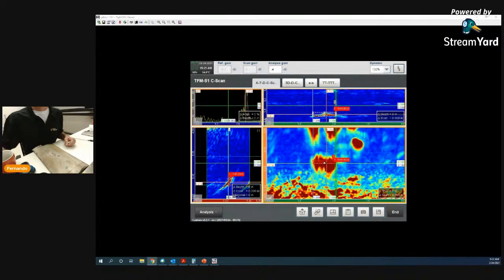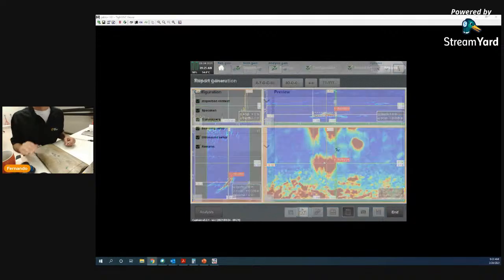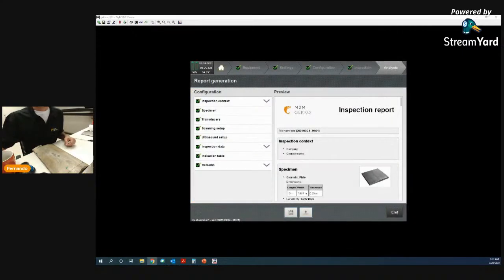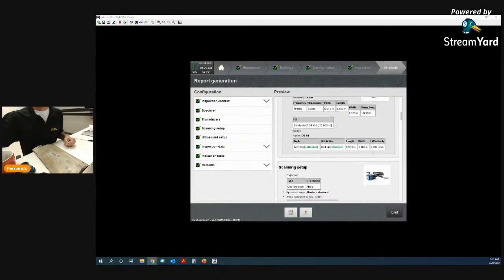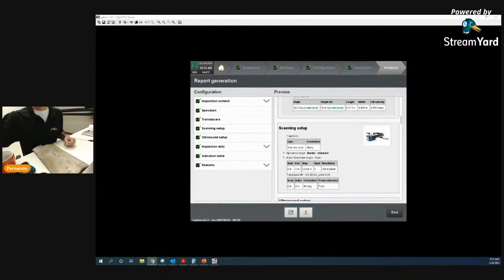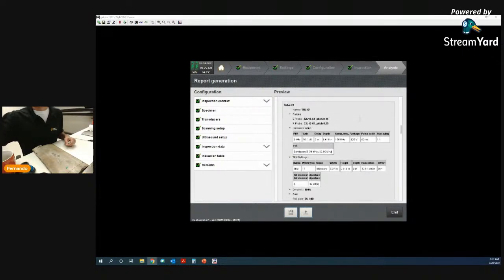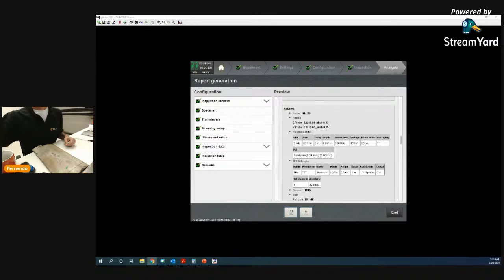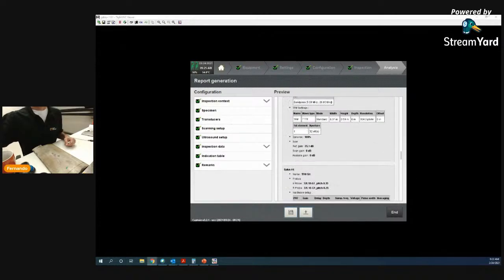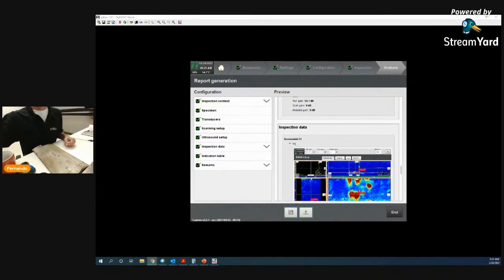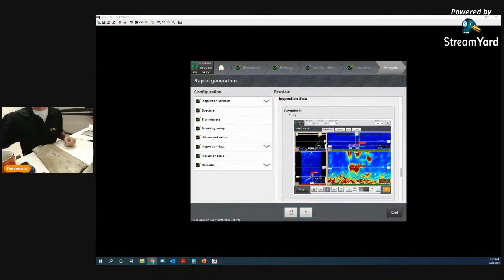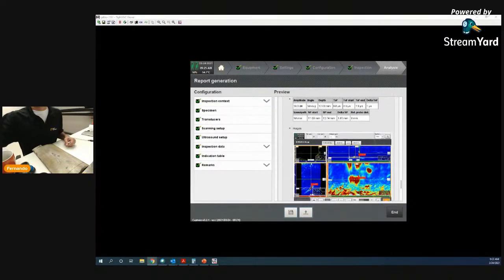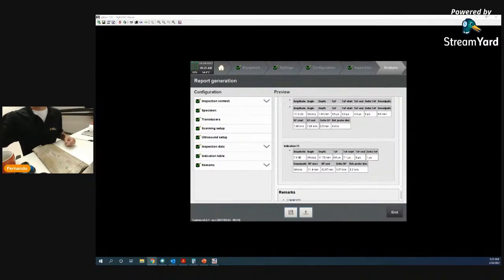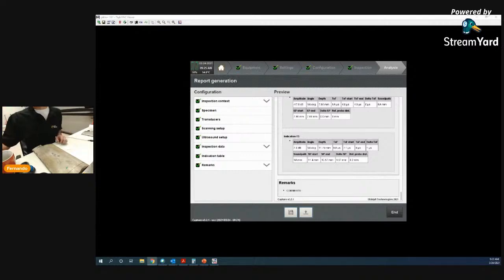So this is where I'm going to select the report. Notice it puts transducer, scan setup, ultrasound setup. It goes through all the parameters. You can see there inspection data, shot number 1, indication number 1, number 2, number 3. I didn't have any pictures for number 2 or 3, but you can see, let's go back.